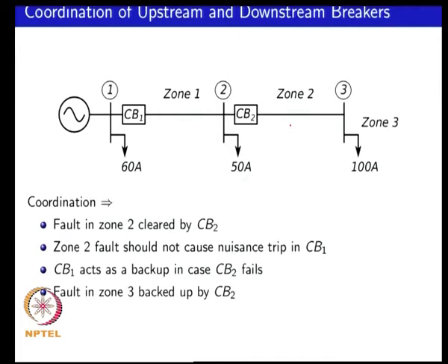be the ranges of fault current levels that happen, whether the fault is occurring close to circuit breaker 1 or further away close to circuit breaker 2, depending on your location, depending on the type of fault, whether it is a three phase fault, single phase fault, whether you have solid fault or some impedance in the fault. You can get a range of current levels that could occur in the circuit, and you want to get a feel for what is the range that you are dealing with.